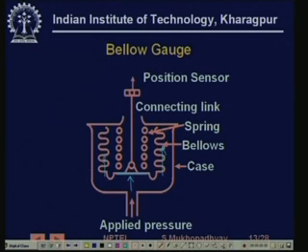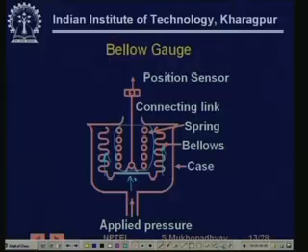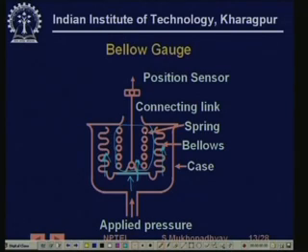In this case, this force will push these up. It's like a spring; there are springs inside, and there are bellows. Bellows are mechanical elements, actually a cylindrical thing which has corrugations. It's a closed surface, and obviously, if there is pressure, this thing will move. So the gaps will close, and this will move up. It is generally used to move up against a particular spring, so that it comes to rest.